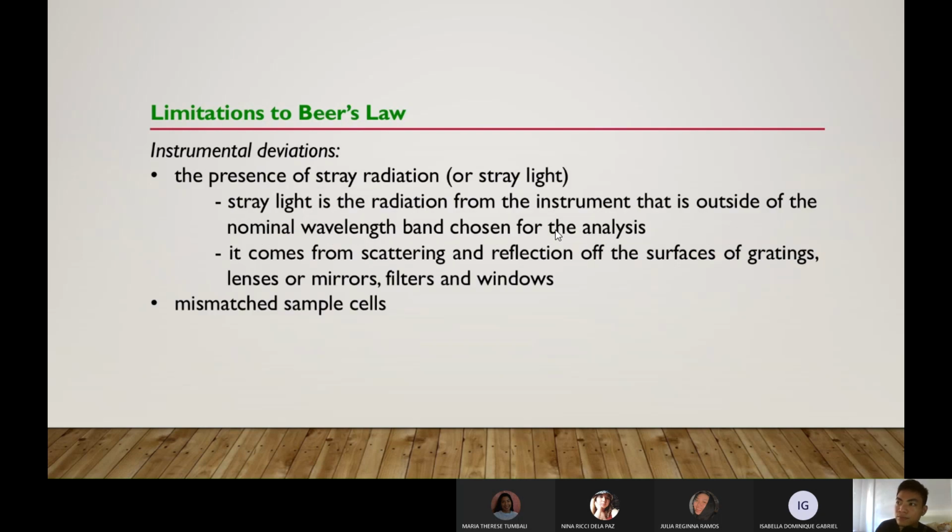Okay. What else? Ayun, ang limitation pa nito is that if you have stray light, no? Ibig sabihin ng stray light, yung liwanag galing sa paligid. So kapag pumasok yun sa spectrometer natin, guguluhin niya yung measurement. So hindi na niya ma-measure accurately yung transmittance. Wala rin, binuksan mo yung spectrometer na yan, papasok yung liwanag sa labas. So, magugulo yung reading mo. So, kailangan when doing spectrophotometry, naka-closed ang environment. Kailangan madilim doon sa pinagme-measurean.